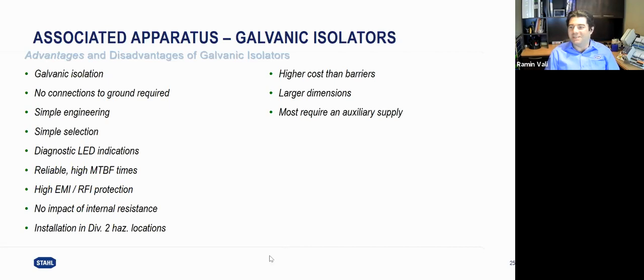Now, because of these features, they are probably a little bit more costly compared to the Zener barriers. They may be large in dimensions because they have a transformer. A few companies like Stahl have a technology to create a very small transformer. So basically, we can have isolators with almost the same footprint as the barrier, but typically galvanic isolators are large in footprint, and they need an auxiliary power supply. So that might be another challenge if somebody wants to eliminate the power supply in a local panel. They better choose a Zener barrier versus an isolator.